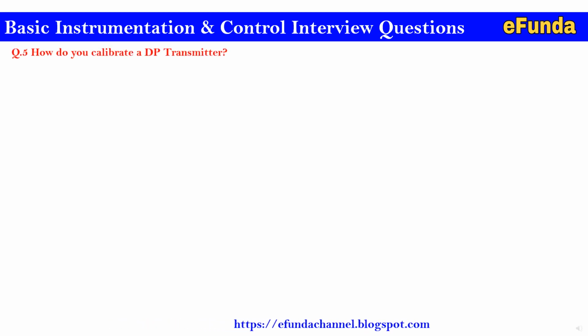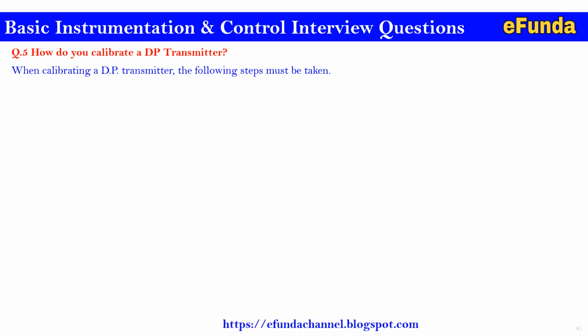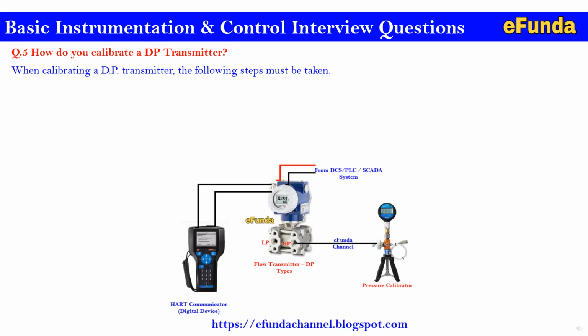Fifth question: how do you calibrate a DP transmitter? When calibrating a DP transmitter, the following steps must be taken. Before that, one can refer to the picture below, where a HART communicator is connected to a flow transmitter, that is a DP type, and a pressure calibrator is being used, and HP and LP connections are shown. Further, 2 wires from the DCS, PLC or SCADA systems are coming to the transmitter, and the same wires carry power from the DCS, PLC or SCADA system as well as the signal from the field to the control system, that is 4 to 20 milliamps. First, set zero to the transmitter.